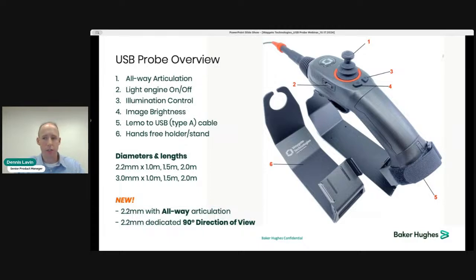And then all new, just launching here, I think this week or next week, is a 2.2 millimeter diameter with all-way articulation. So with that 360-degree articulation, previously it was only 2 ways. So you had one of those old fiberscope type knobs to go 2 ways, but now you get that 360-degree, and you'll have that ergonomic joystick. Also new on the 2.2 millimeter is a dedicated side view 90-degree probe. So if you're getting those really tight applications where you don't have room to articulate over, you have a 90-degree dedicated probe so you can see, for example, the wall of a tubing.